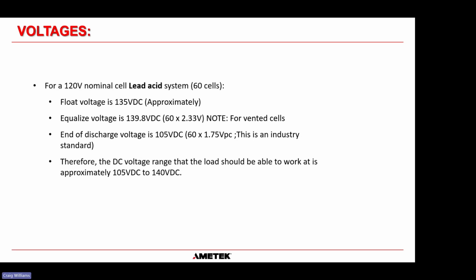The end of discharge voltage for a lead acid battery is usually stipulated at 105 volts DC. That is a standard that's been chosen by engineers over time, and that is 60 cells times an end voltage of 1.75 volts per cell. In truth, you can discharge a lead acid battery down to 1.6 volts per cell if you really wanted to. But the battery manufacturers say that if you go past 1.6 volts per cell, you may be causing irreversible damage to the lead acid battery. So that's why this safe margin of error was given, and we discharge batteries down to 1.75 volts per cell, which is a total of 105 volts for a 60 cell system.